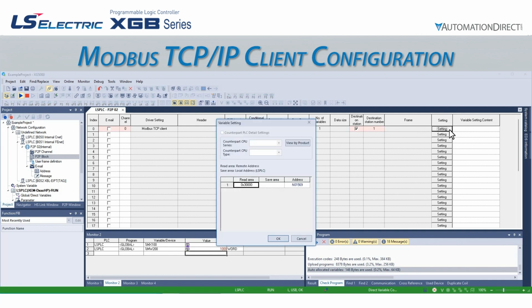The last field is the variable setting content. We configure this by clicking the Setting button. This opens the Variable Setting pop-up window. Because we aren't doing communications from one LSPLC to another over the XGT protocol, we don't use the counterpart CPU area. The read area is the memory location in hex that we will read the data from in the server, and the save area is the direct variable address to which the XGB PLC will store the information. The address area is automatically assigned by the PLC, so we will leave it alone.